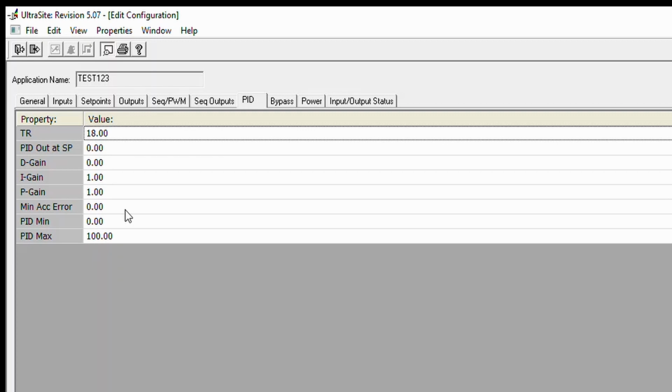Once you get it to where it's within a degree or 2, or maybe 4 degrees around that set point, you're going to want to start adding some I in. You start with like 0.20 of I. What that does over time is it starts to add I or subtract I from the equation, and then it starts to smooth out the equation. So instead of this choppiness, you get this nice, even, almost straight line. So that's how you're going to want to do it.